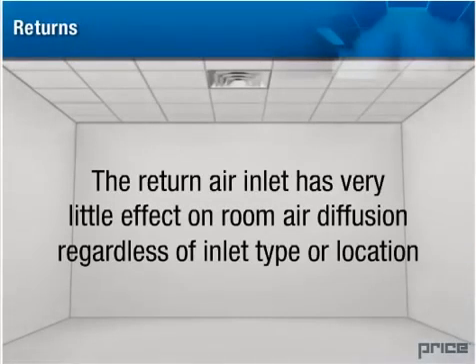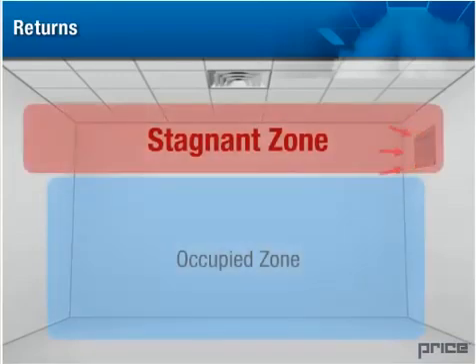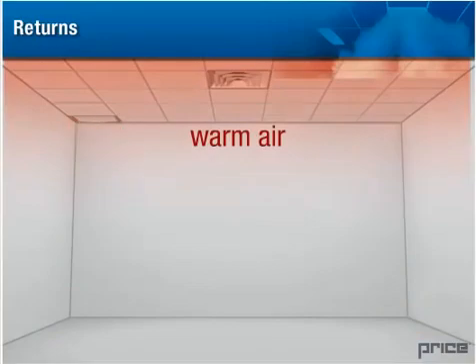The return air inlet has very little effect on room air diffusion, regardless of inlet type or location. However, return air inlets should be located a sufficient distance from the supply outlet so that short circuiting of supply air does not occur. It may also be desirable to locate the returns in the stagnant zone to remove unwanted warm or cool air. For cooling, a high sidewall or ceiling return will remove warm air from the space.